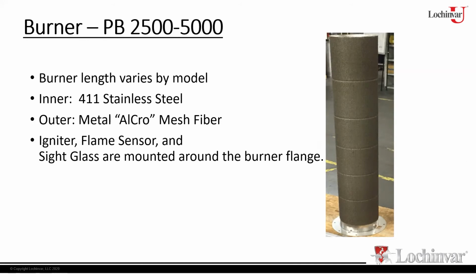You're going to blow them out with air. As you see the burner sitting here, basically you want to hold it upside down so the opening is at the bottom. You blow the air through the burner from the outside in, so that way you're reversing the pressure back through the mesh. A lot of times people will stick their hose down the inlet of the burner, if you will, trying to blow through it.